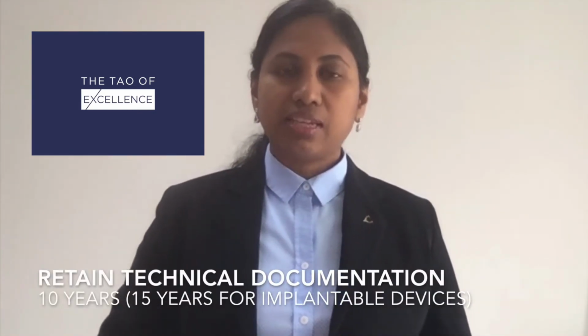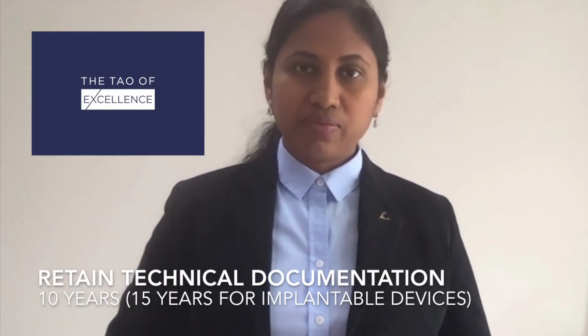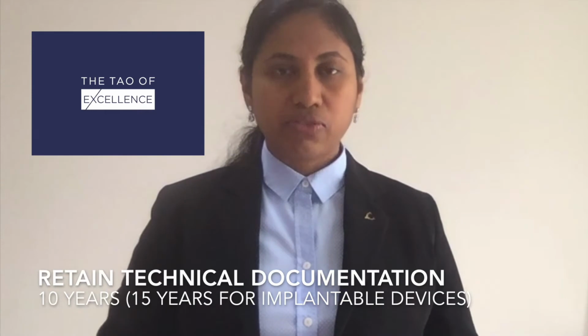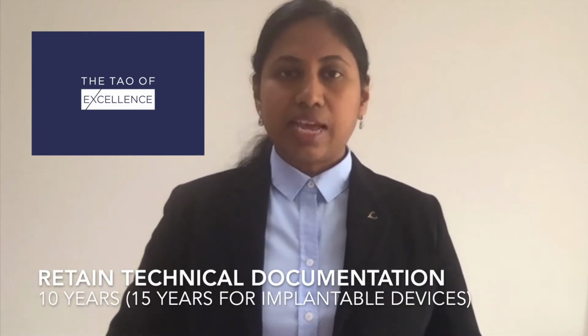Let's talk about the retention period of the documents. The manufacturer should retain the documents, that is the EU Declaration of Conformity, the technical documentation, and if any, certificates, for a period of 10 years from the time the last device has been placed on the market. This time period extends to 15 years for implantable devices. When requested by a competent authority, the manufacturer shall submit the technical documentation completely or a summary as requested.